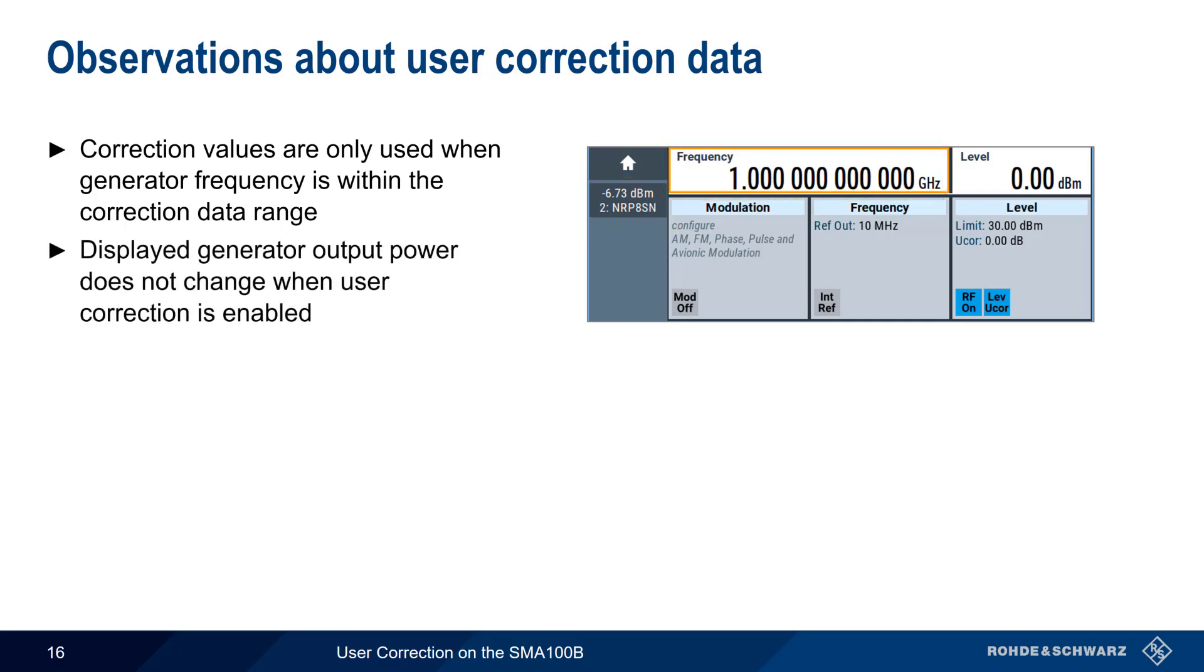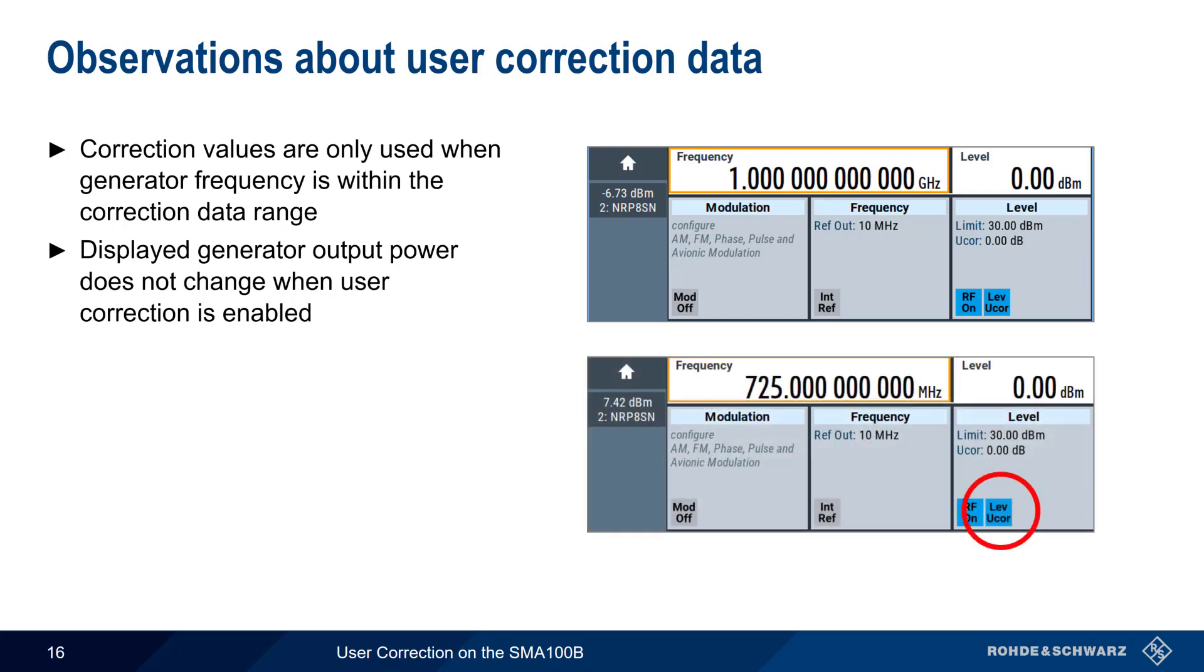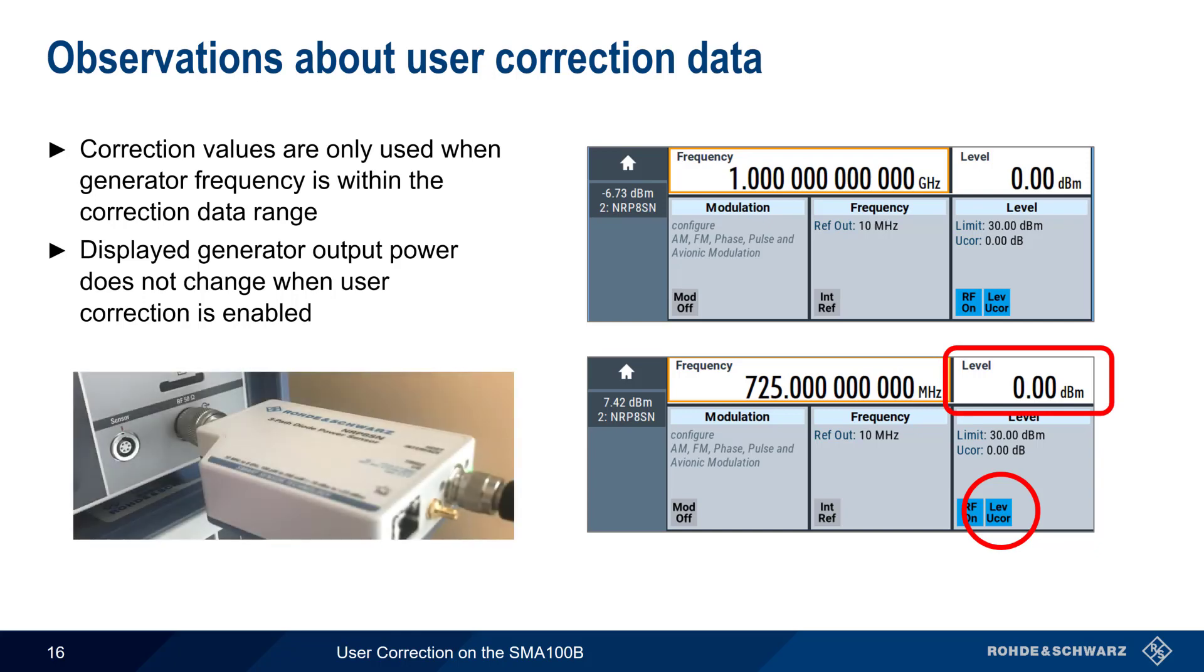Secondly, note that the generator's displayed output power does not change even when user correction is enabled and active. Here, we are within the frequency range covered by the correction values and user correction is enabled. The SMA shows our generator output power as 0 dBm, but a directly connected power sensor shows that the actual SMA100B power output is plus 7.42 dBm.